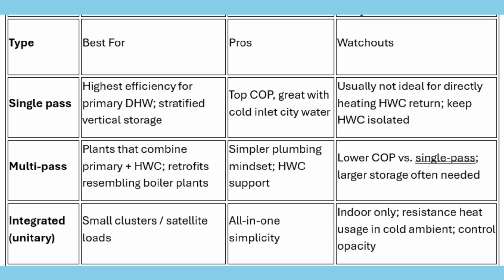Finally, which HPWH to buy for your building or for domestic hot water application. Single-pass units are the efficiency leaders for primary domestic hot water. They love cold city water and work best with tall, stratified vertical storage and a downstream mixing valve. Multi-pass units excel when the hot water circulation loop returns warm water to the plant. They can heat that loop well, though overall efficiency is usually lower than single-pass.